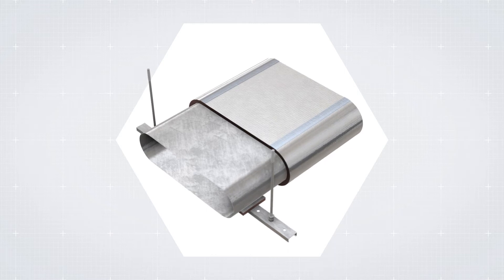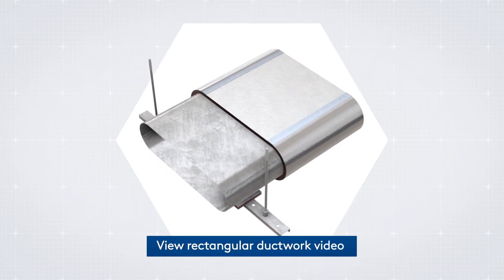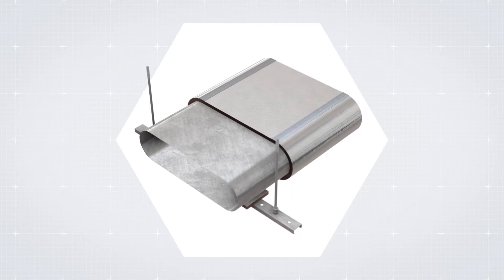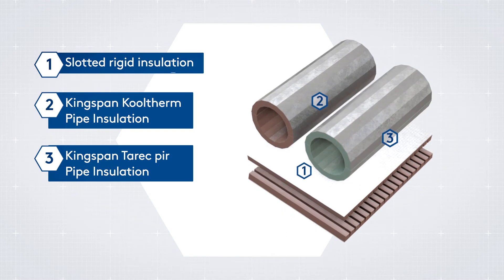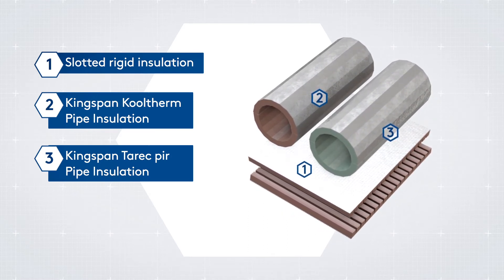To insulate flat oval ductwork, you must insulate the flat areas as per instructed for rectangular ductwork, and insulate the curved areas as previously explained. To insulate oval ductwork, you either use slotted rigid insulation, Kingspan Kooltherm pipe insulation, or Kingspan Tarec pipe insulation.